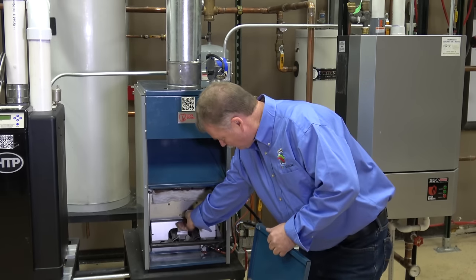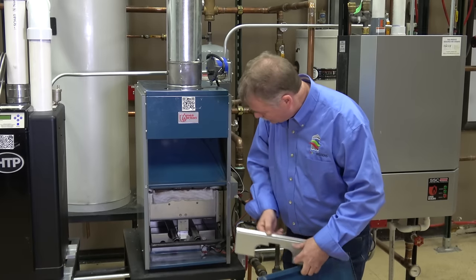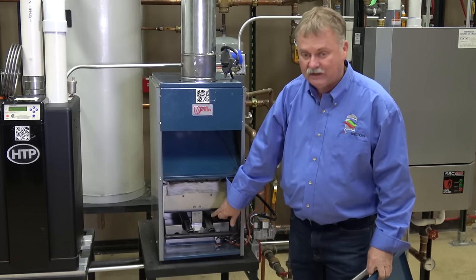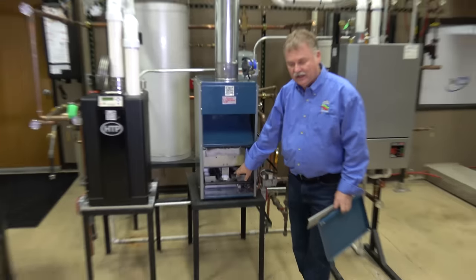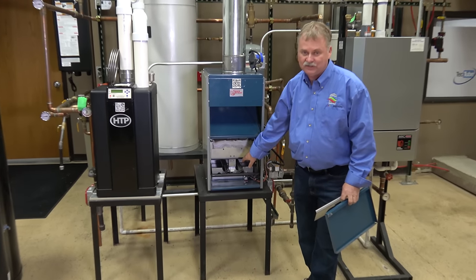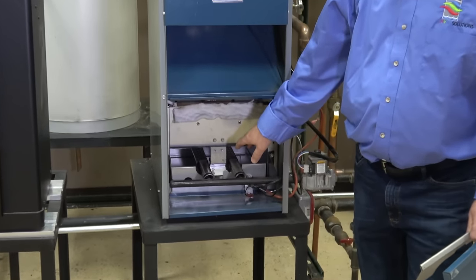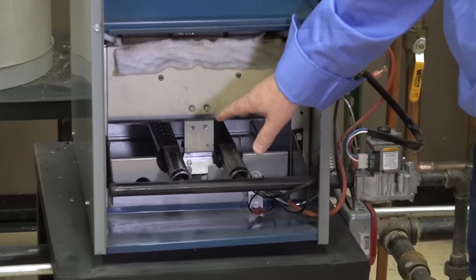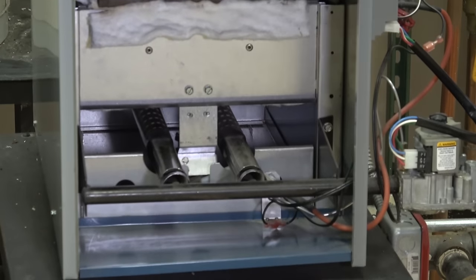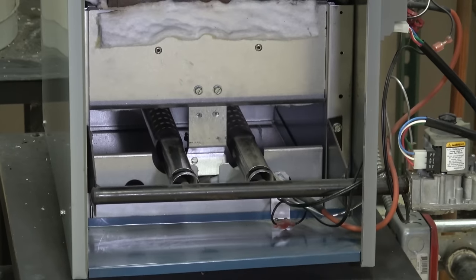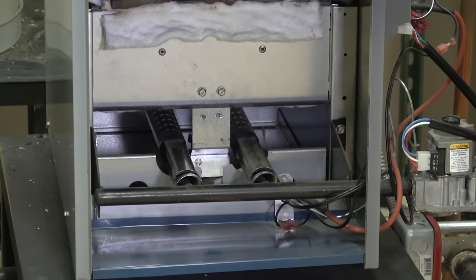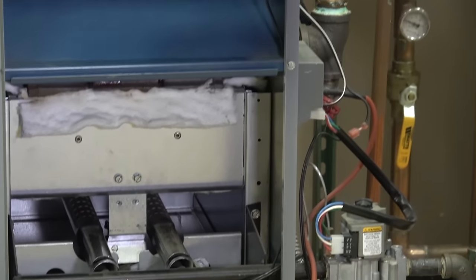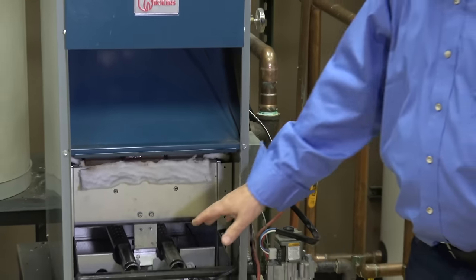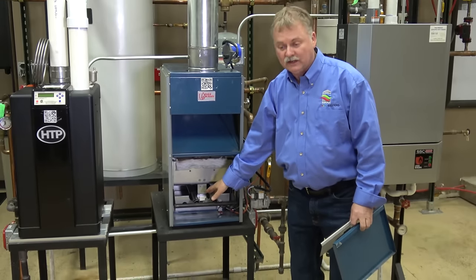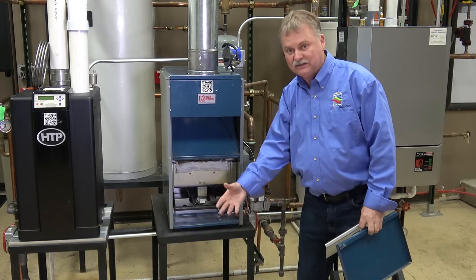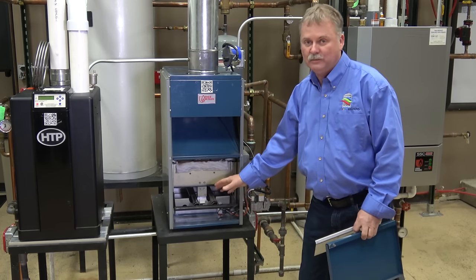Burners are right behind this little burner door here. In typical systems, you have a spark igniter and a flame rectification probe, or in the old days they called it a thermocouple. You get a call for heat, the vent damper opens, it goes through a few safeties to make sure the water temperature's correct and a few other things, and then we'll light off the burners. This is atmospheric in design because this boiler uses room air.